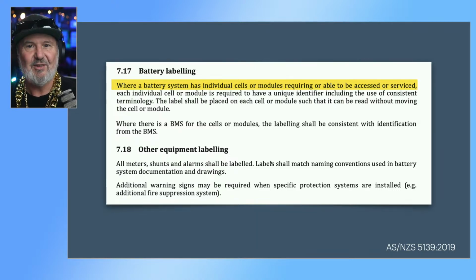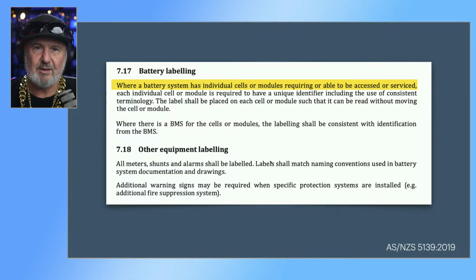That's great. So, yeah, it's one of my pet hates. So, battery labelling. In the standard 5139, it says where a battery system has individual cells or modules that are able to be accessed or serviced, each individual cell or module is required to have a unique identifier, including the use of consistent terminology. So battery 1, battery 2, battery 3, or module 1, module 2, module 3, if you've got a rack of them. The label shall be placed on each cell or module.